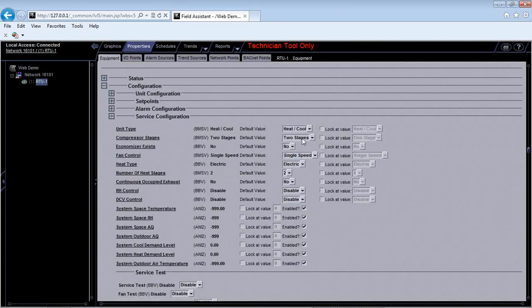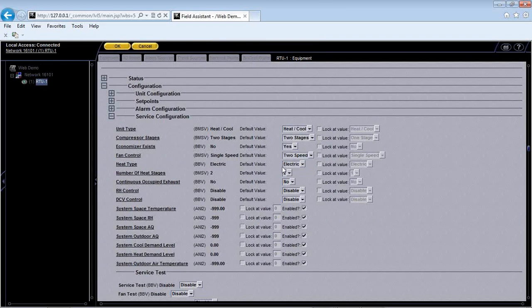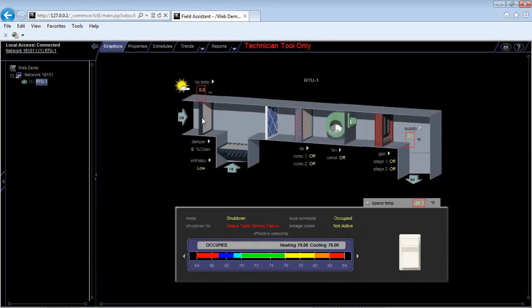So I have 2 stages of DX. I want to add an economizer, and I want to add 2-speed fan control, and we usually have gas rooftop units with 2 stages. Okay, so I want to hit OK here. If I look at my graphic, now you can see I have an economizer. You can see my 2 dampers. I have 2 stages of DX.